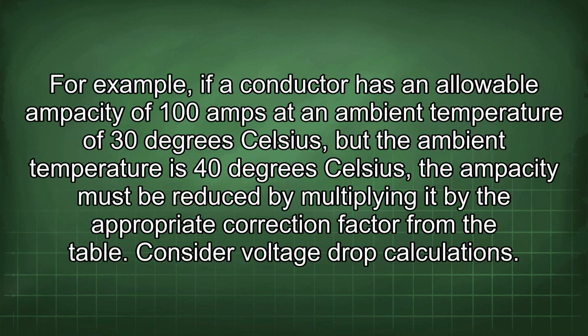For example, if a conductor has an allowable ampacity of 100 amps at an ambient temperature of 30 degrees Celsius, but the ambient temperature is 40 degrees Celsius, the ampacity must be reduced by multiplying it by the appropriate correction factor from the table. Consider voltage drop calculations.